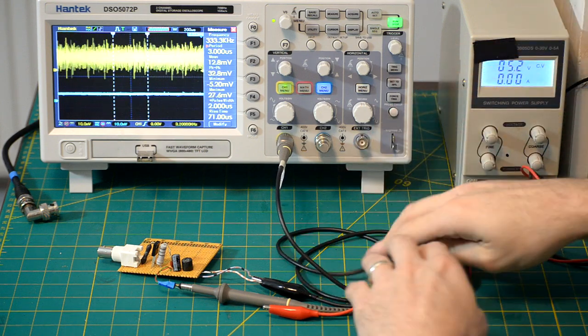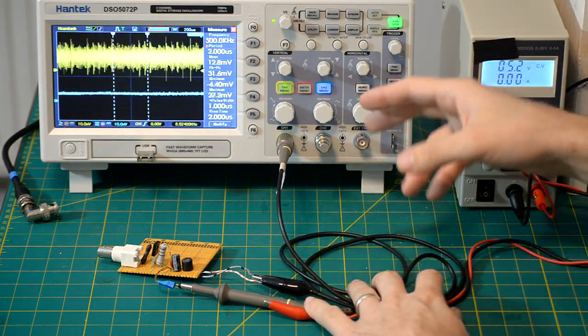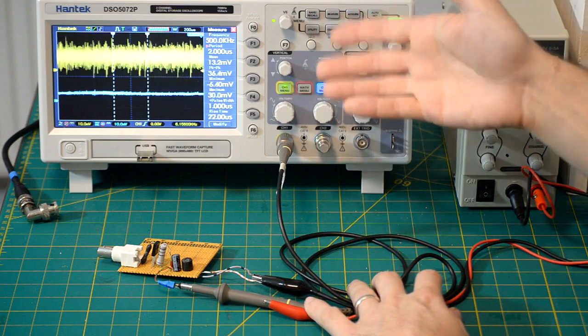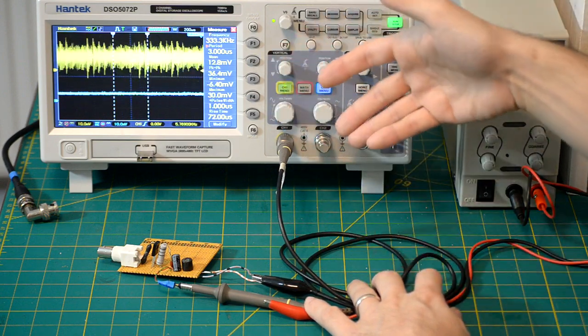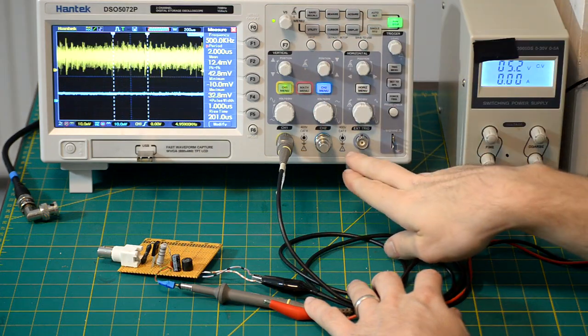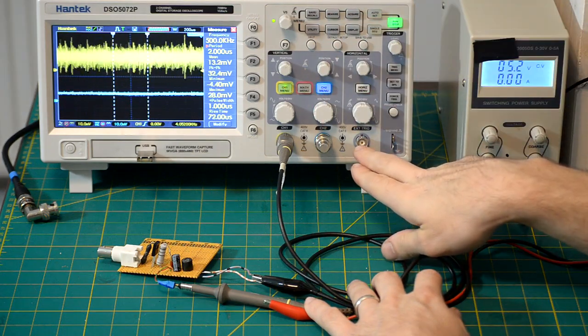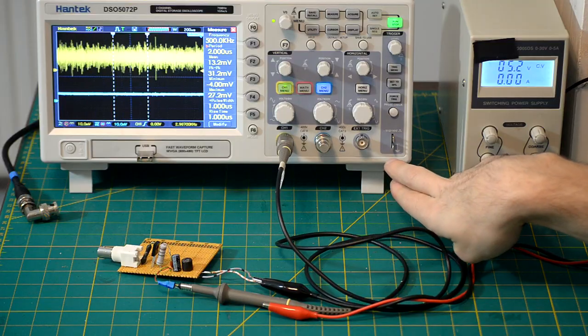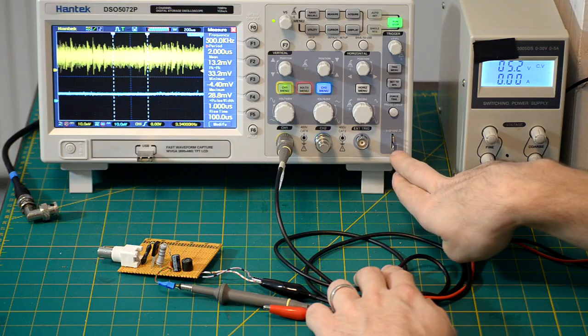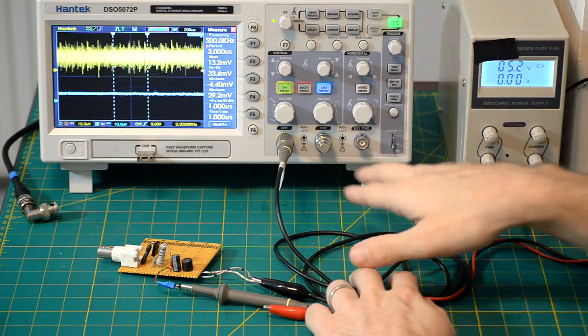And now one of the things that you will observe on any oscilloscope is that the ground of all of the inputs is interconnected, but usually you'll be using it for your probes. You also have an external trigger input, which is not very commonly used, and you also have this calibration output. This is a calibration signal that you can use to calibrate your probes, but this also has a ground pin. So what I want to do is take the ground directly from the oscilloscope and connect it to the power supply through a shorter line and try to reduce the noise this way.